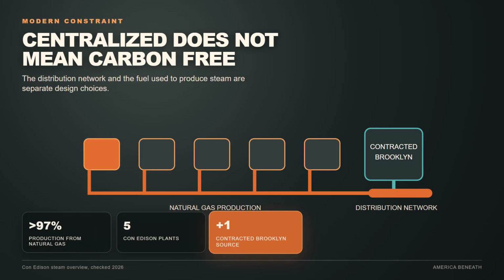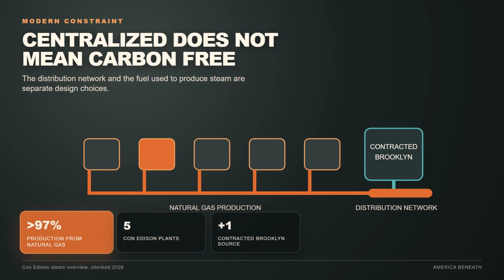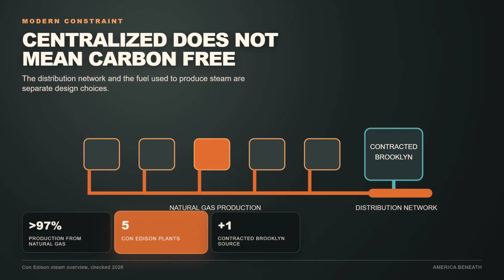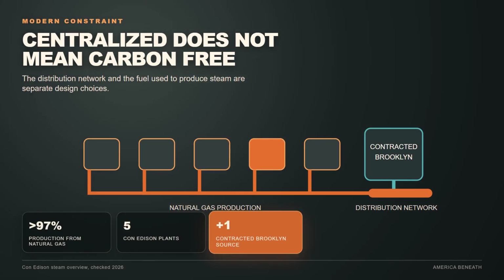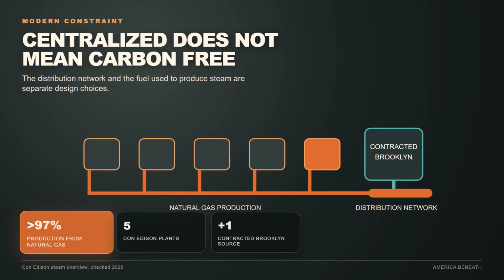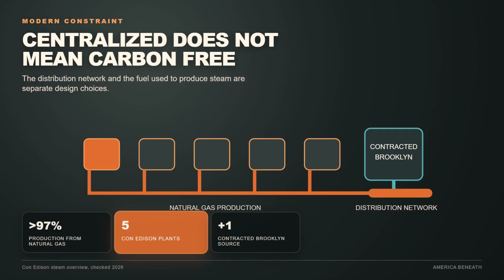That distinction opens 2 broad directions. One is to replace steam service building by building, moving more production equipment and energy demand inside each property. The other is to keep useful parts of the distribution system while changing how the steam is produced. Real planning can combine those directions, and the right answer can vary by customer. This episode cannot prove which path will win. What it can show is why the question is more difficult than old technology versus new technology. Electrifying a building is not merely a fuel swap if the building also needs new equipment, electrical capacity, and distribution work. Decarbonizing central steam is not merely a pipe question if the production plants remain dependent on natural gas.